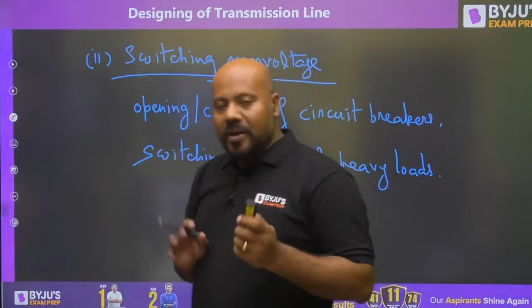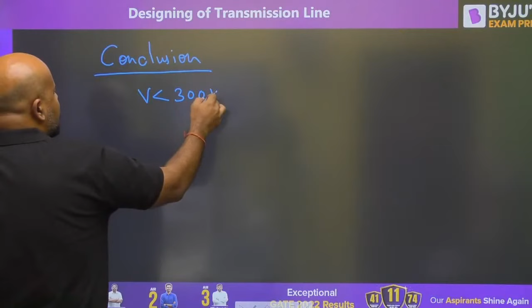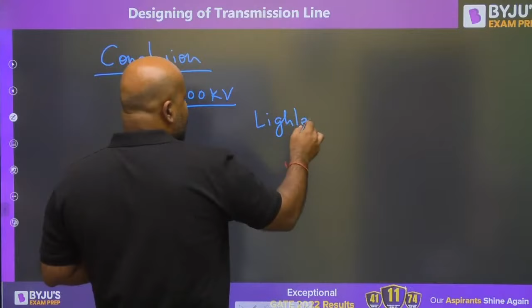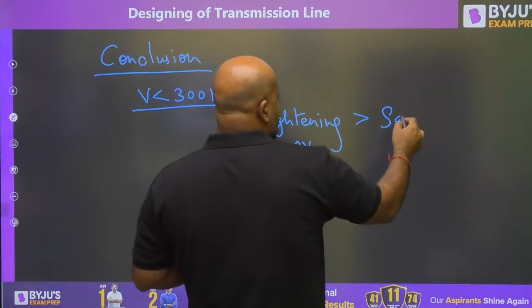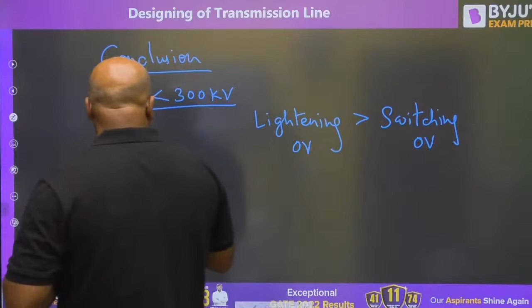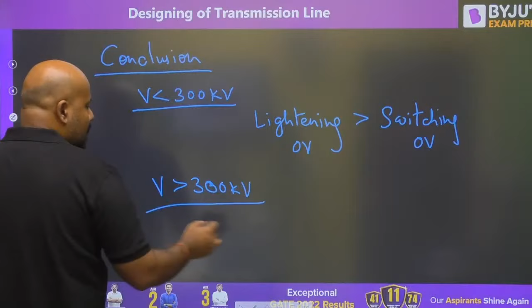In general, you can conclude that for voltage less than 300 kilovolts, lightning over voltage is going to be more dangerous than switching over voltages. But for voltages more than 300 kilovolts, switching over voltages are the deciding criteria for insulation level.